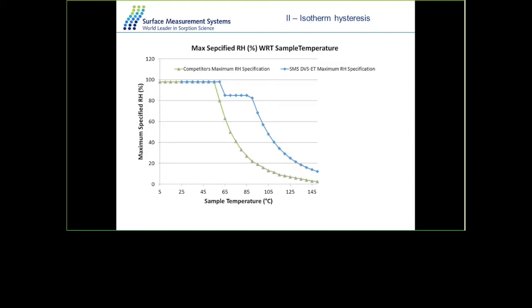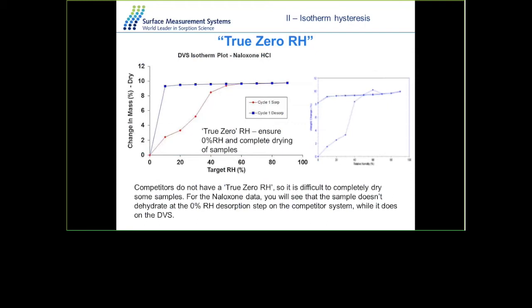Another advantage of the SMS product is the true zero RH capability. Using Naloxone HCl as an example, with a competitor system the desorption curve doesn't return to zero during the drying process, whereas with the SMS product the desorption curve returns to zero due to the true zero RH property of the system.